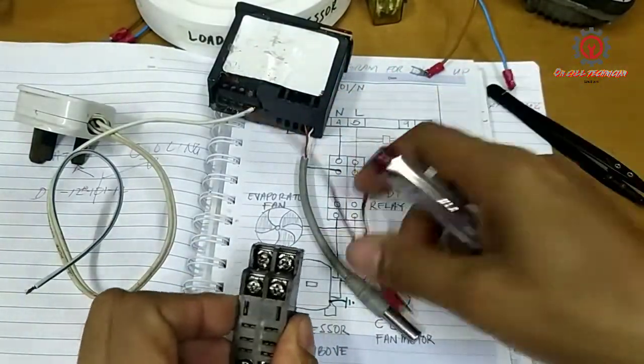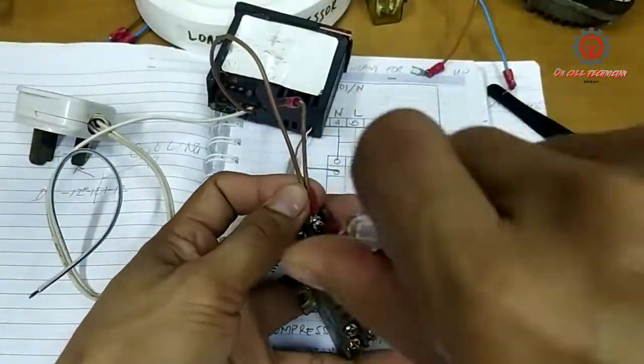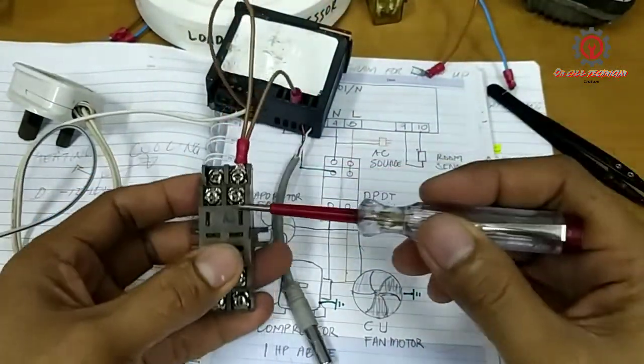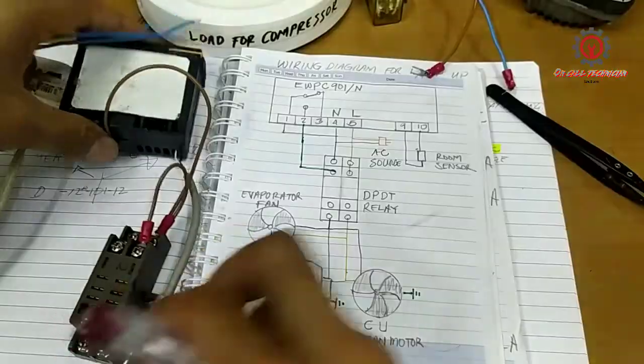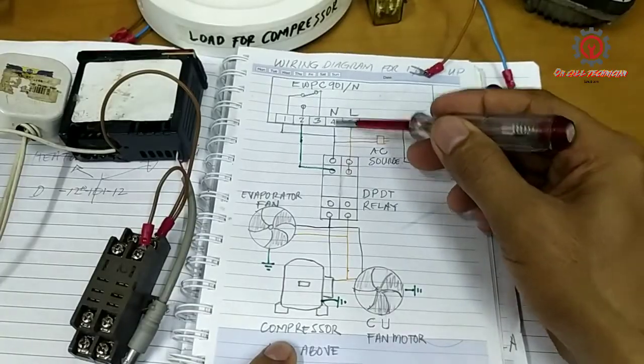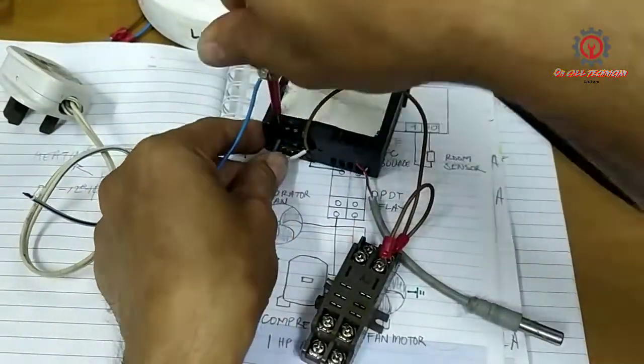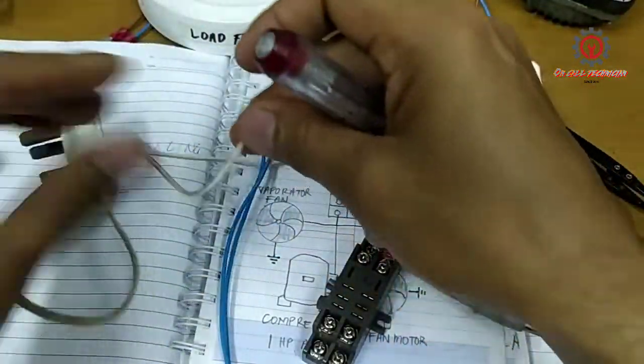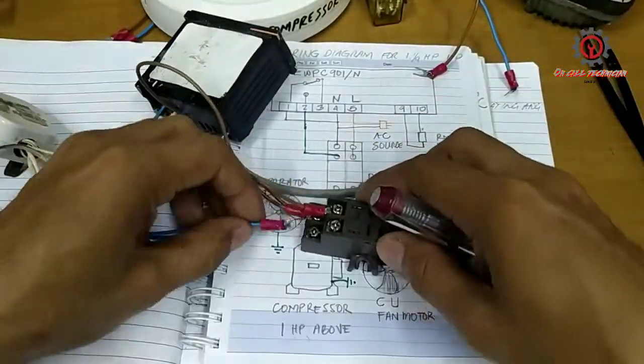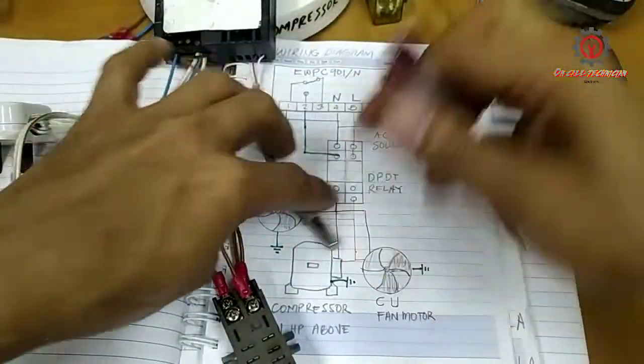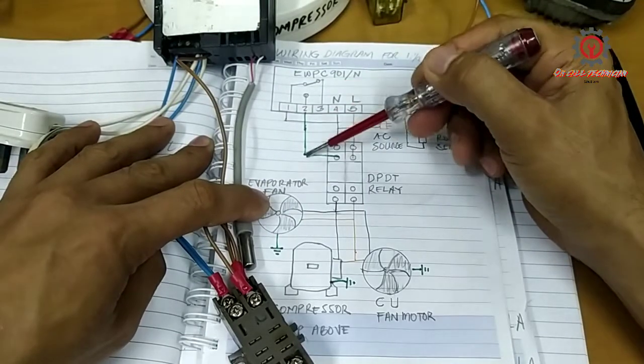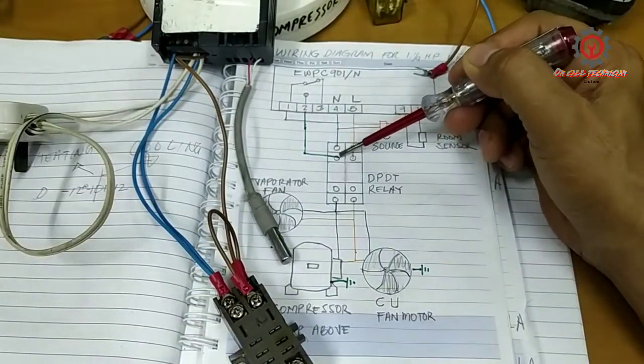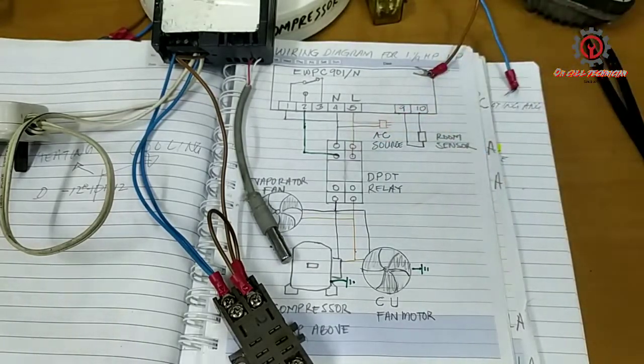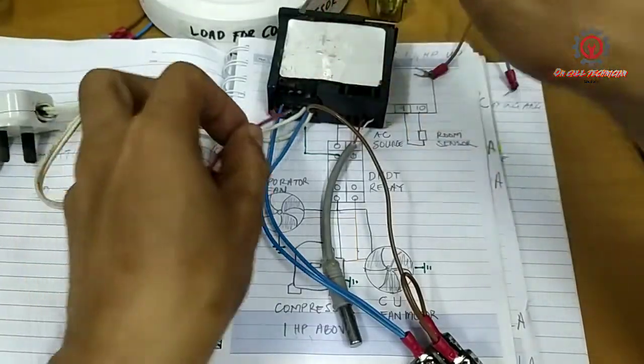Connect the line, and this will be my live. And we are going to supply the coil of the relay. Okay guys, neutral, AC line 4 and 1, together with my AC plug, and this is my neutral. Neutral here, and last but not least, the line for the compressor supplies the other side of the coil. Terminal number 2 is for the compressor.